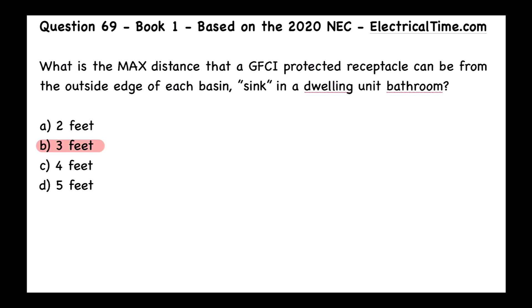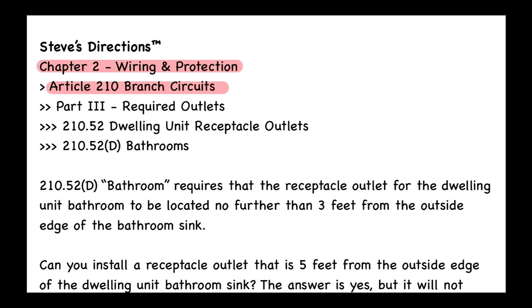One section is GFCI protection, which is 210.8. The other covers the maximum distance, found under a different section of Article 210. That maximum distance is found in Part 3, called Required Outlets, specifically 210.52 for dwelling unit receptacle outlets, and then 210.52(D) for bathrooms.